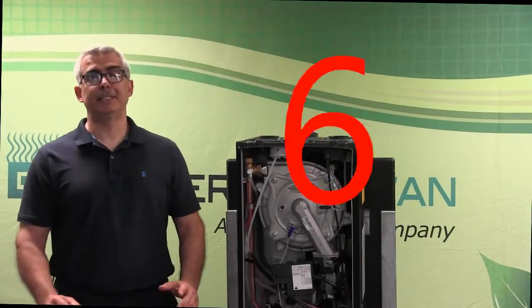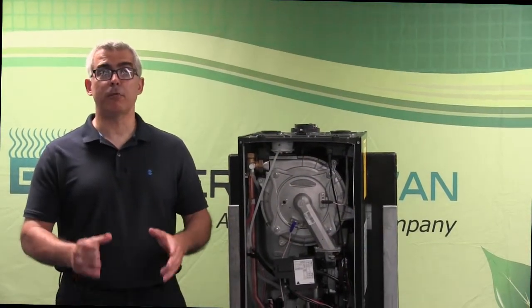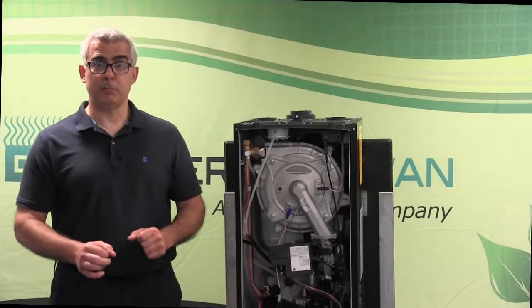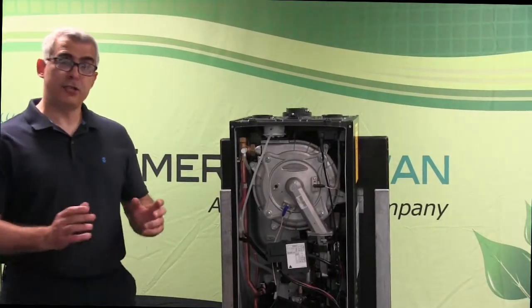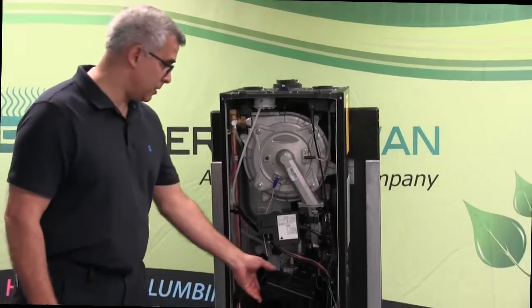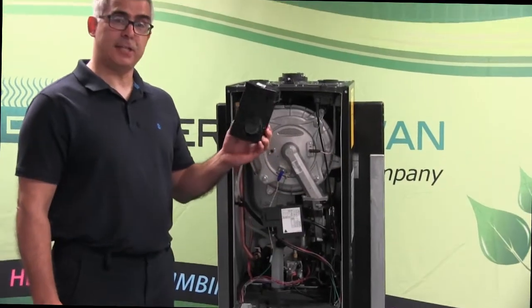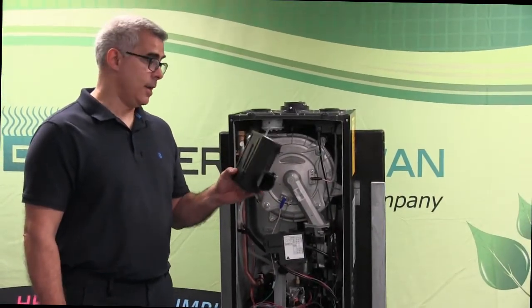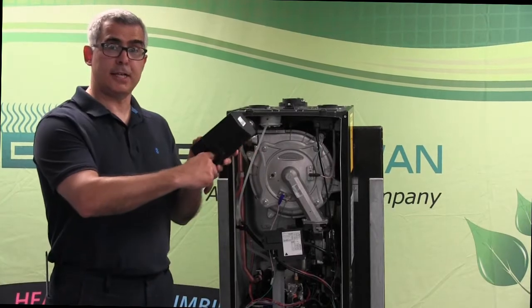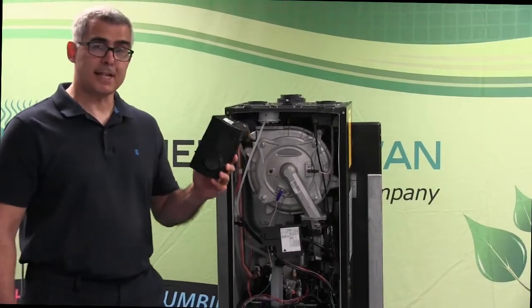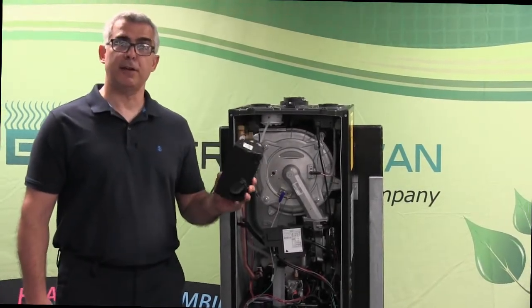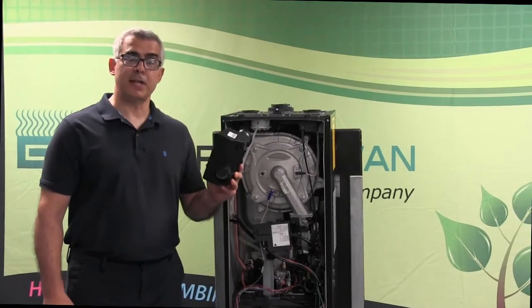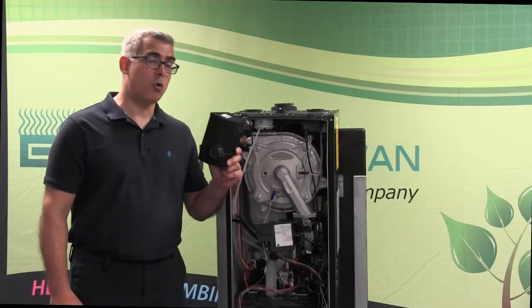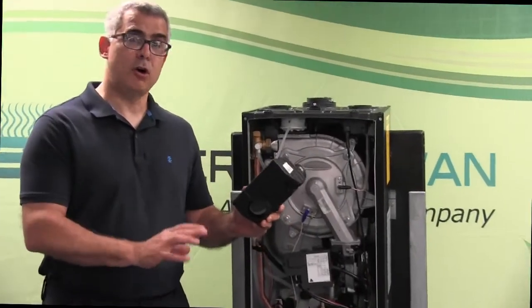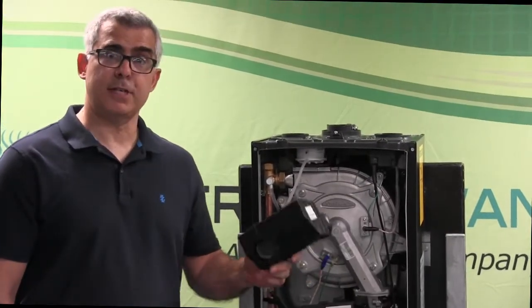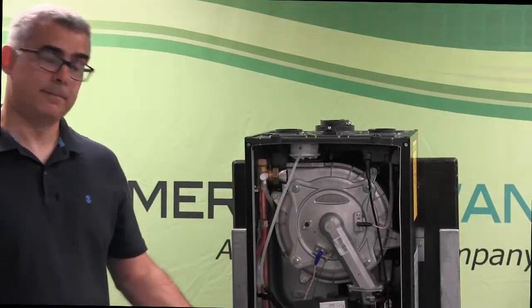Number 6, sealed cabinet for quiet operation. 40 decibel noise level. These units come with a muffler. This is the muffler right here. It's attached to the intake of the blower fan. And what it is, it has insulation in it. And the number one thing, I've started about 30 of these boilers with different contractors, and all of them have mentioned how quiet this runs, how quiet it starts. So all 8 Ariston boilers come with the muffler system.